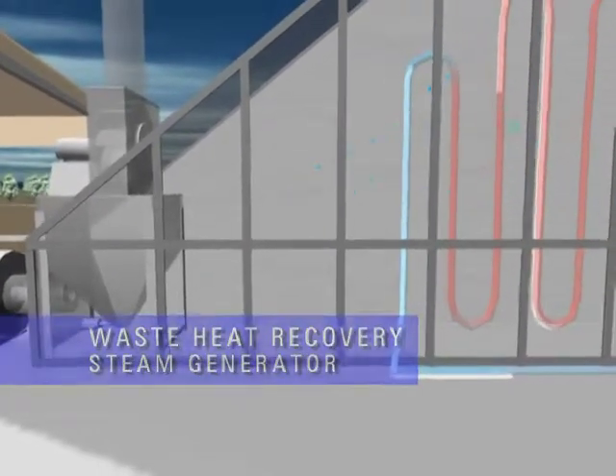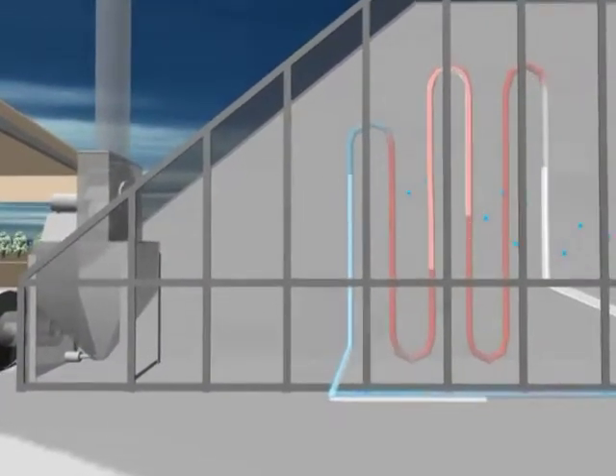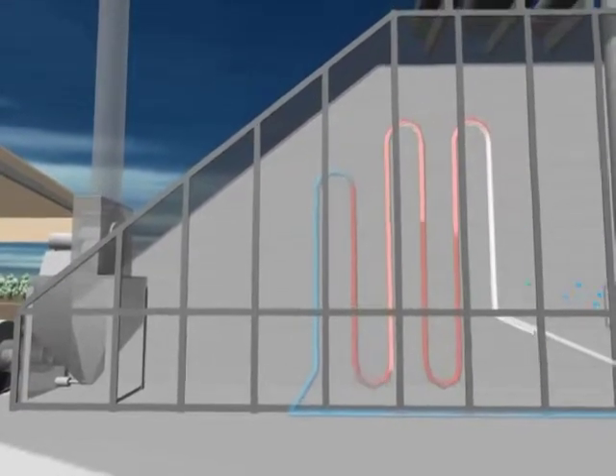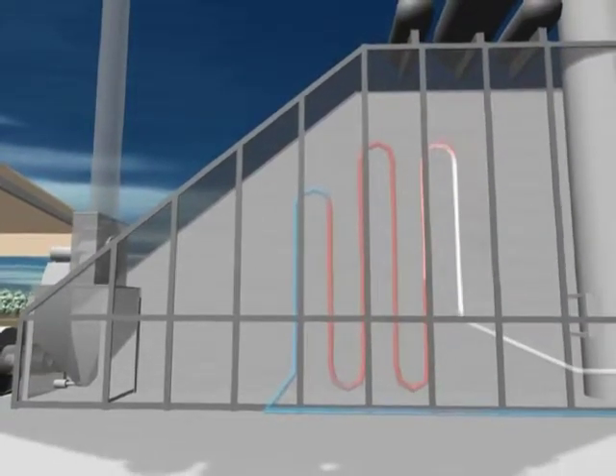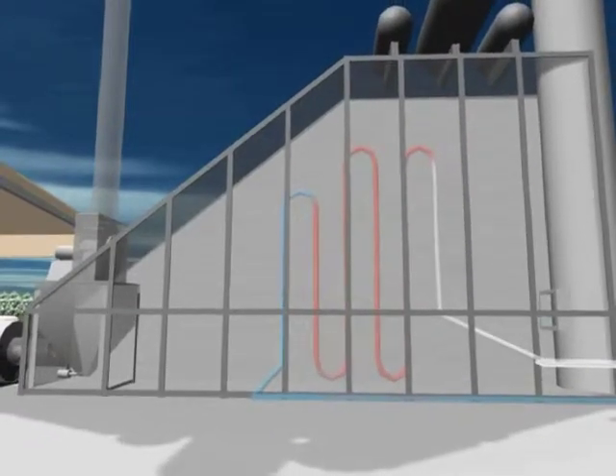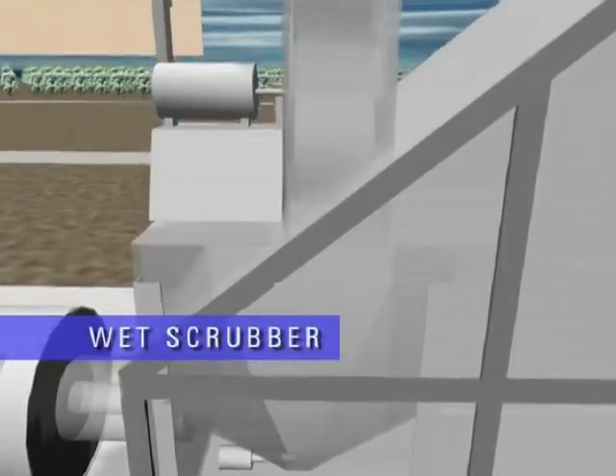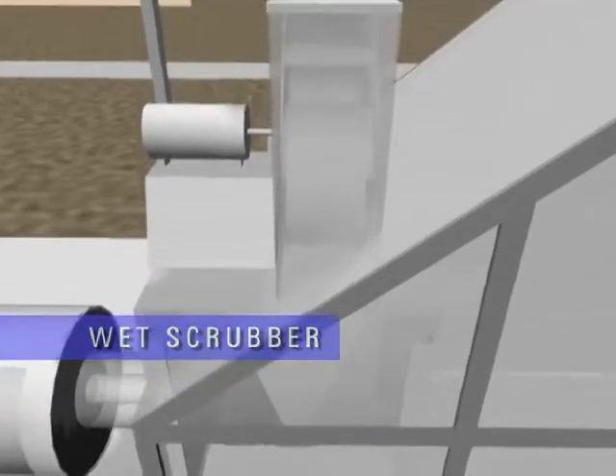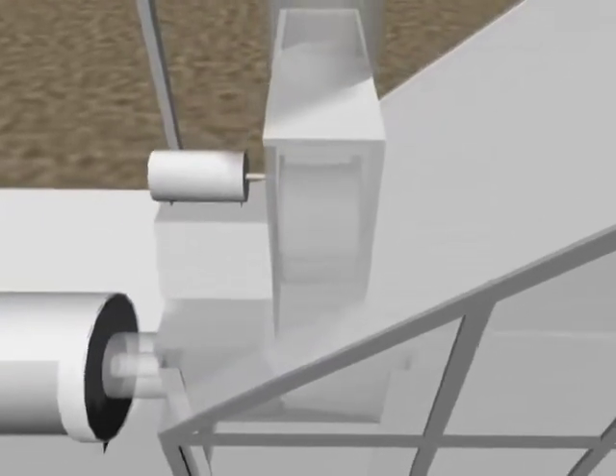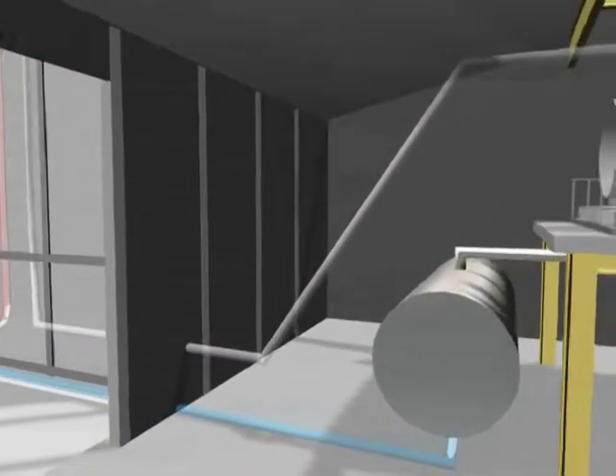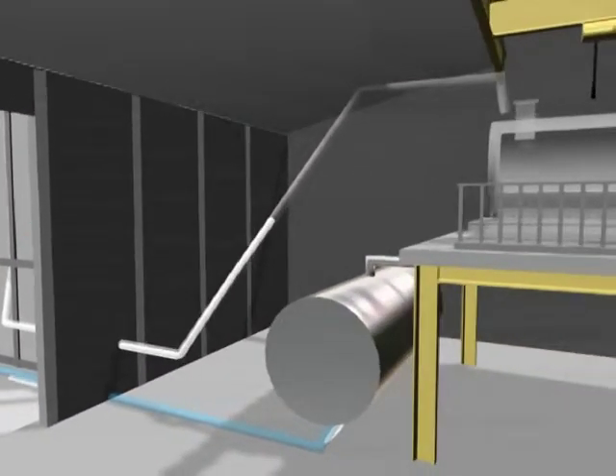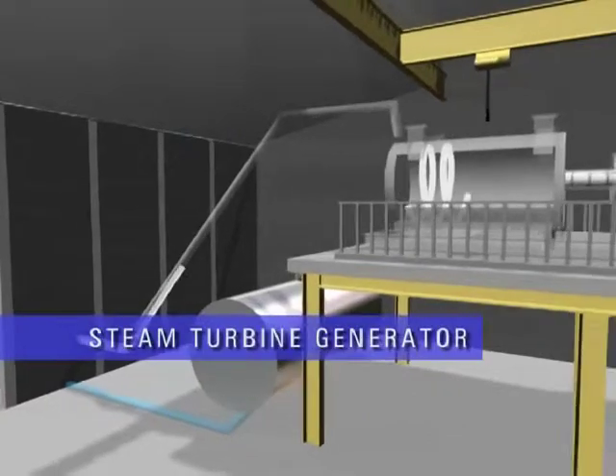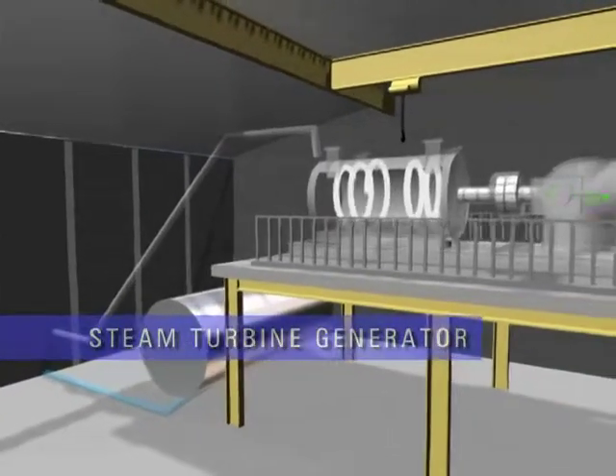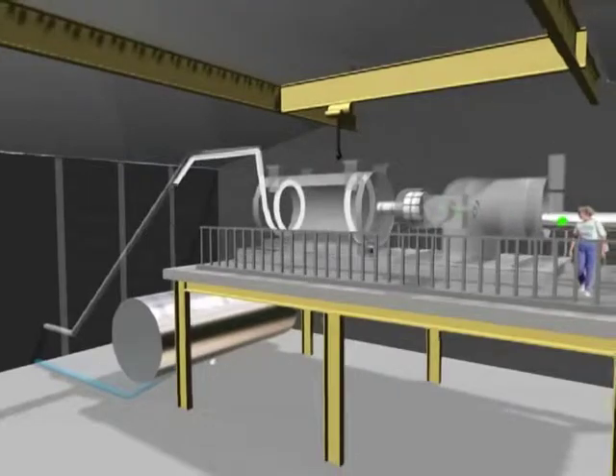The waste heat recovery steam generator captures this useful thermal energy and converts this energy into high-quality steam at 650 degrees Fahrenheit and 750 psi. Finally, the exiting flue gases pass through advanced NOx control and a wet scrubbing system, rendering it completely safe and harmless for permissible emission into the environment. The high-quality main steam generated flows through a common header to the inlet stop valve of the steam turbine generator, which converts it to electrical power for distribution into the municipal electric system.